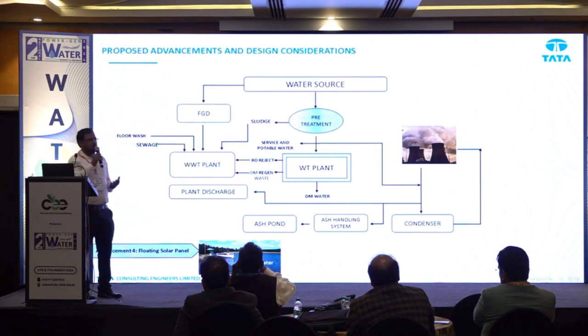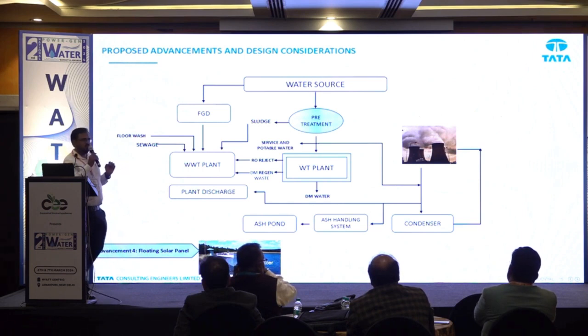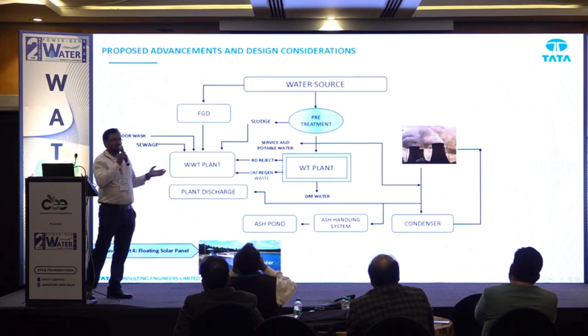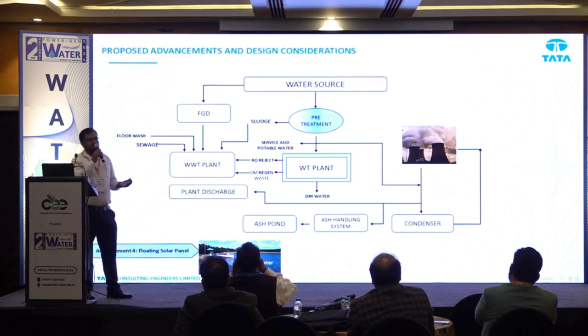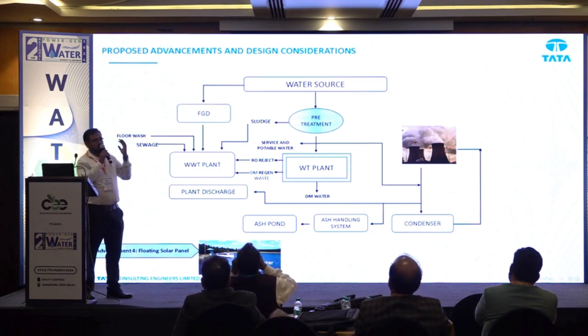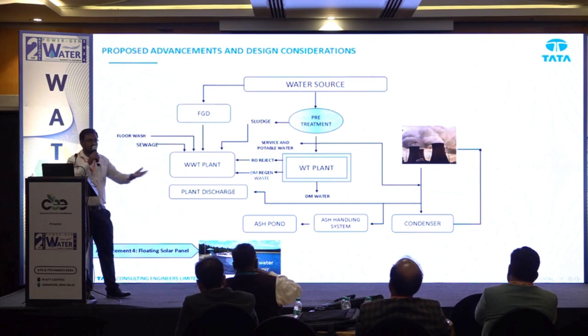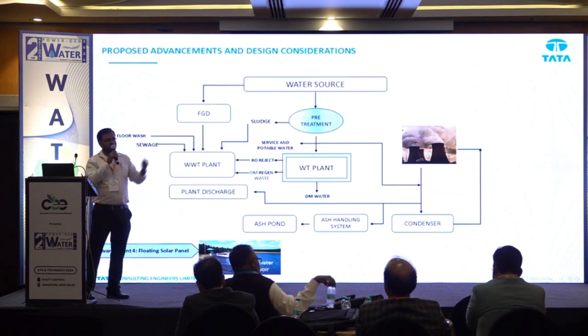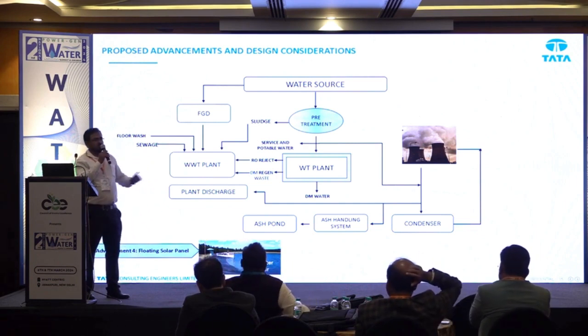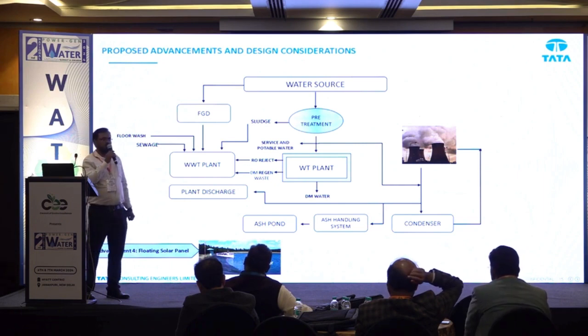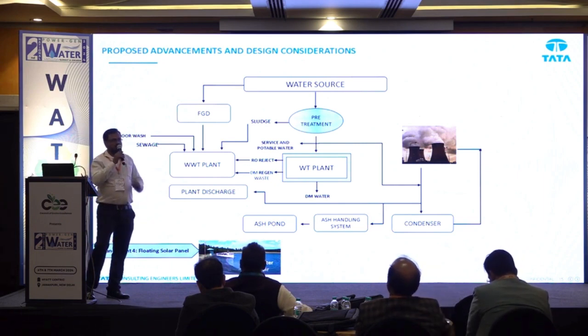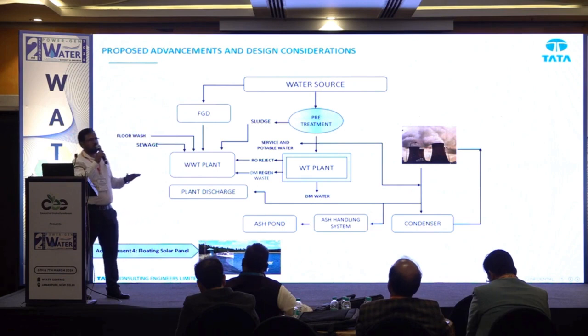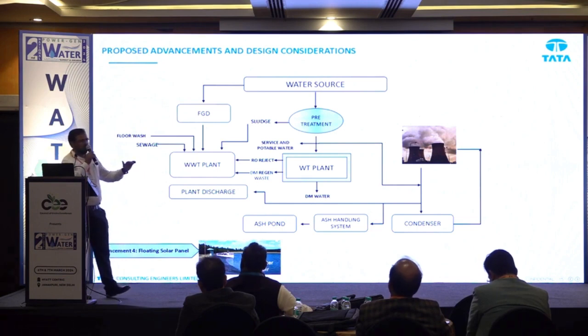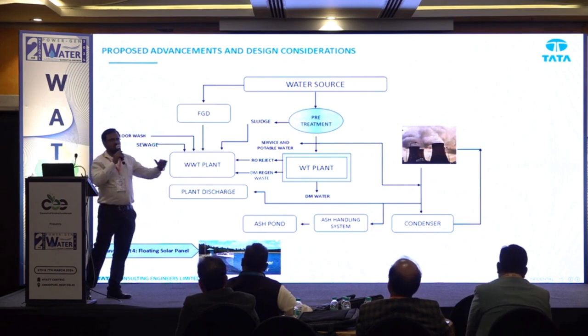It is huge. So many things can be done with these 4 advancements, and we are sure that down the line, as we are working and evaluating, one day will come where people will say the wet cooling tower system is more efficient. Here also, we are now able to reduce the water consumption from 2.1 meter cube per hour to 0.6 to 0.7 meter cube per hour, even 1 meter cube. So fine, this wet cooling tower is the solution.